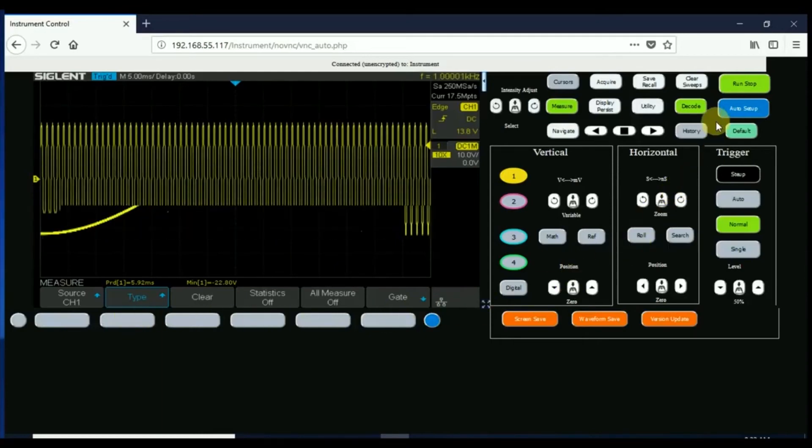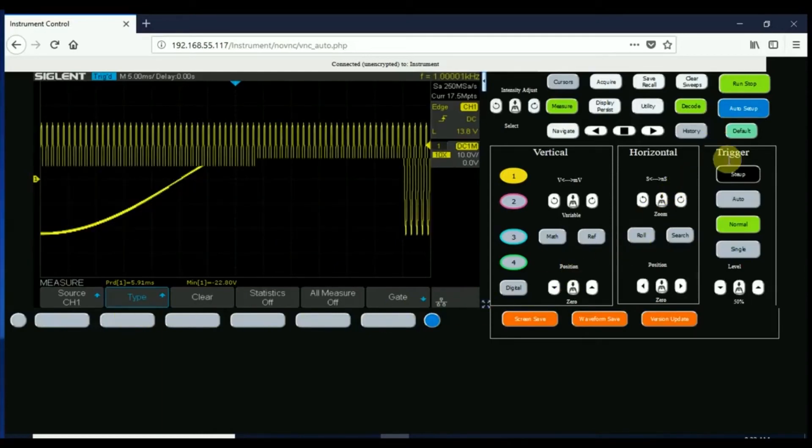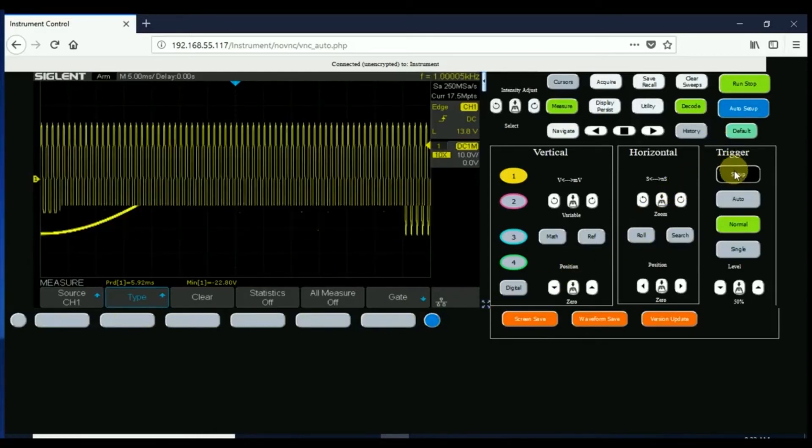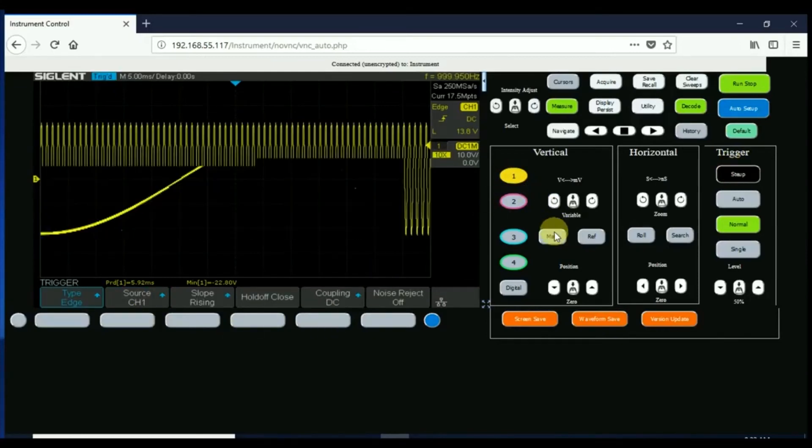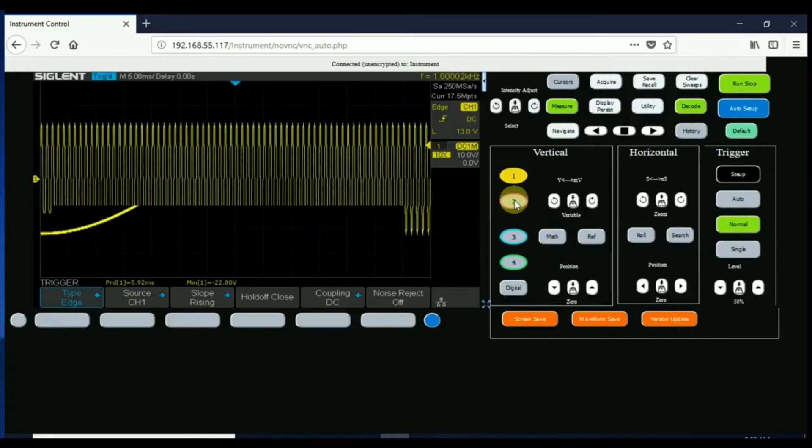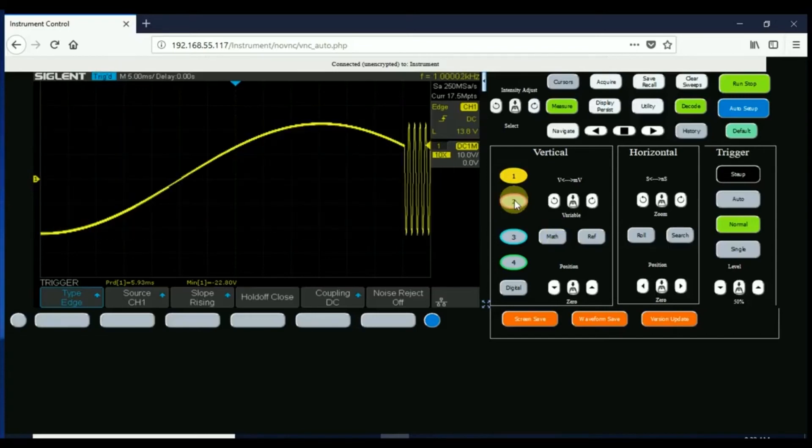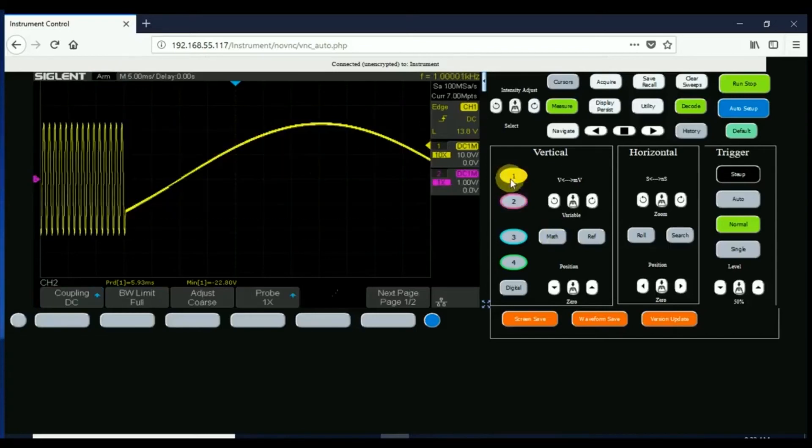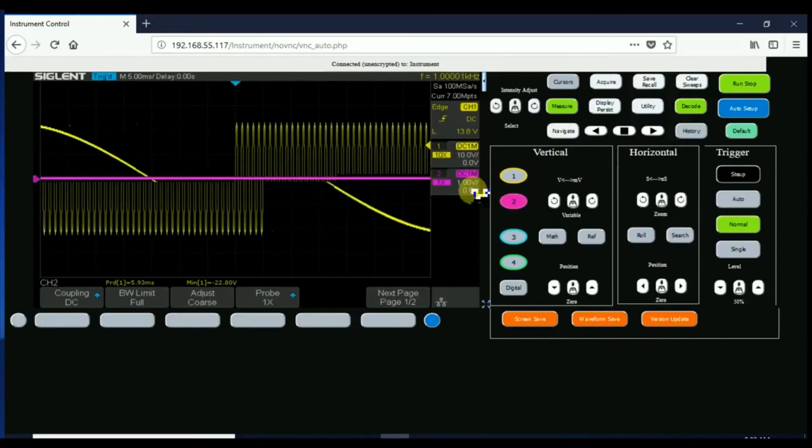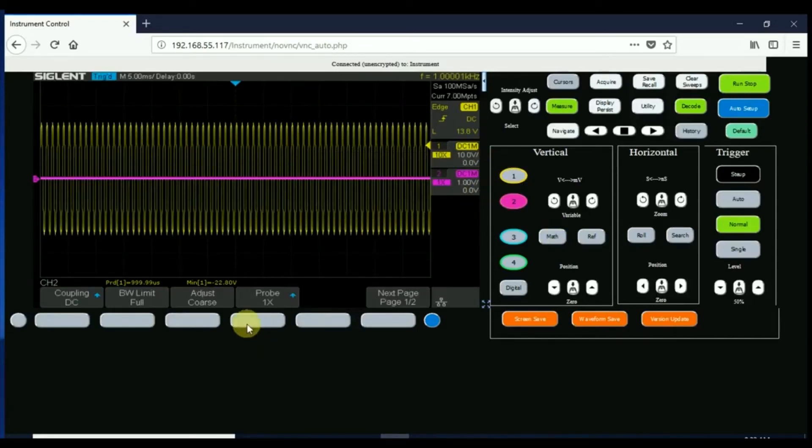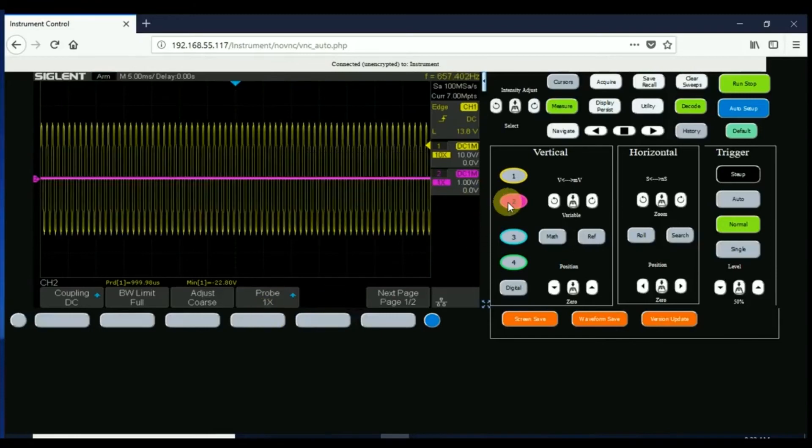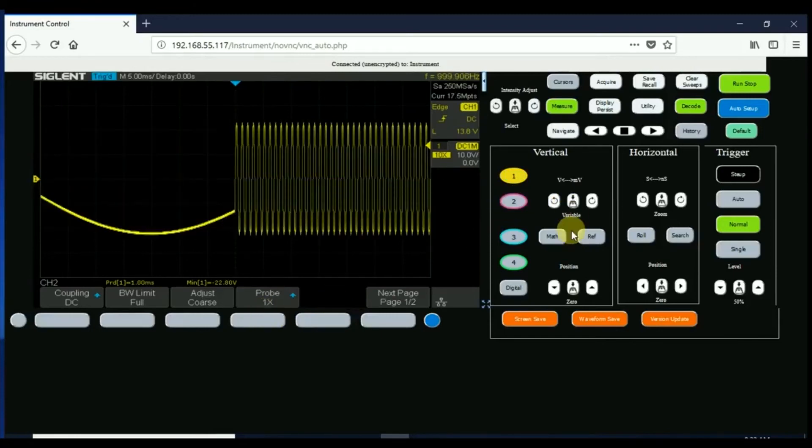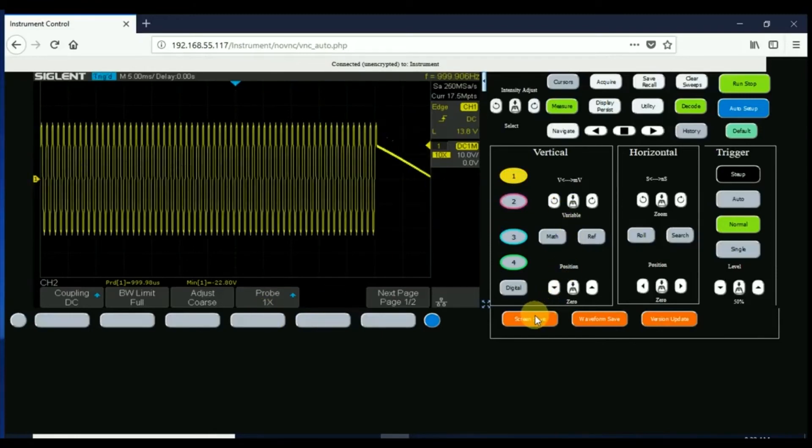You can control each of the channels, you can control run stop, you can control the trigger menu as we've shown here. So basically everything you have the ability to do on the front panel of the oscilloscope, you can do it remotely here through this web interface, and really the important thing here is how fast it's updating.